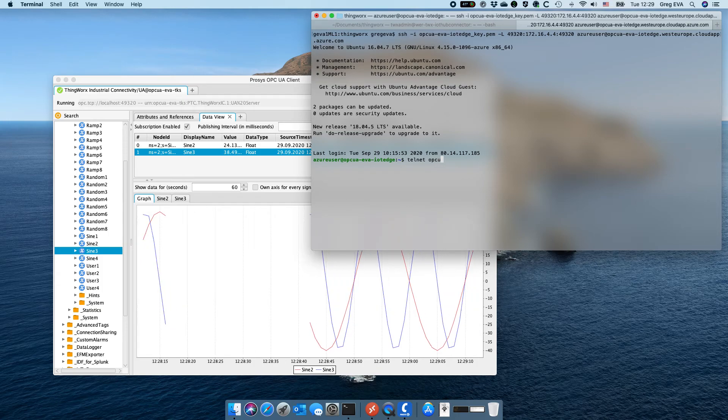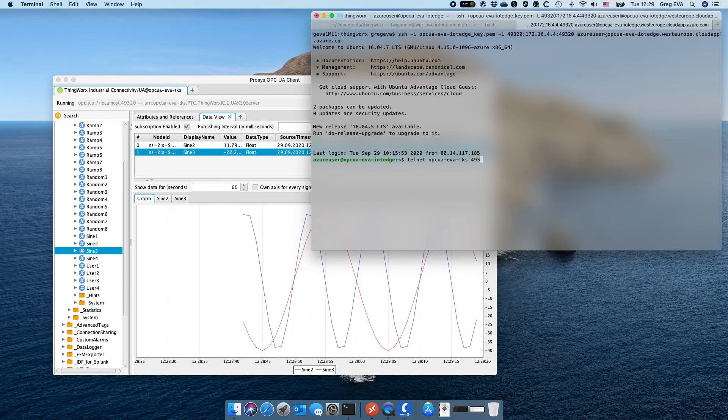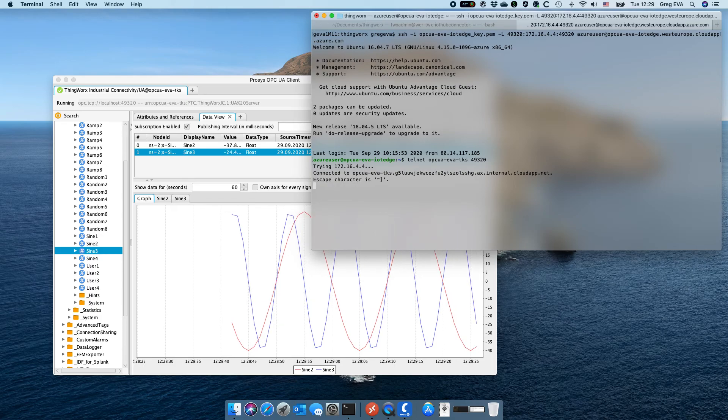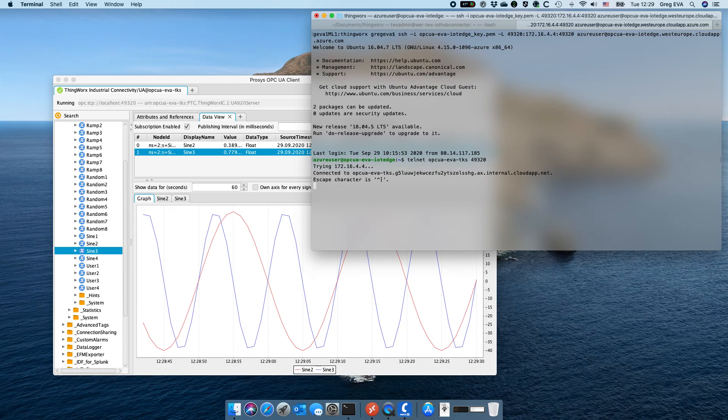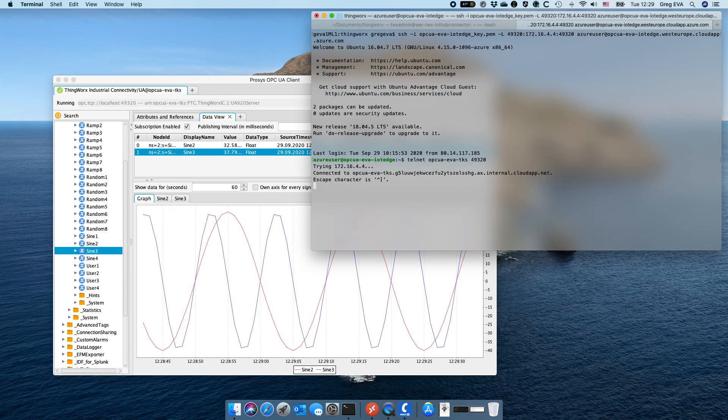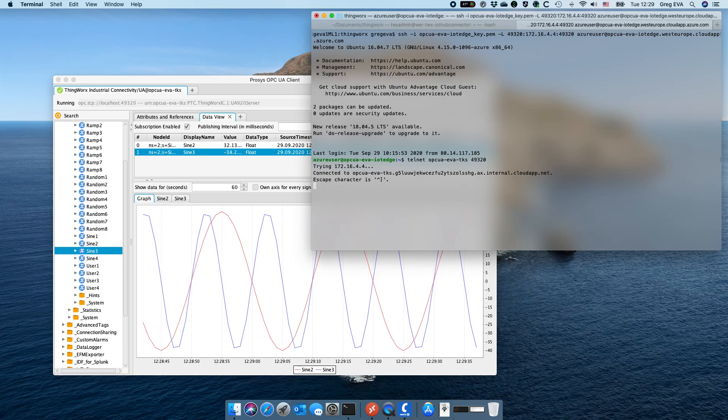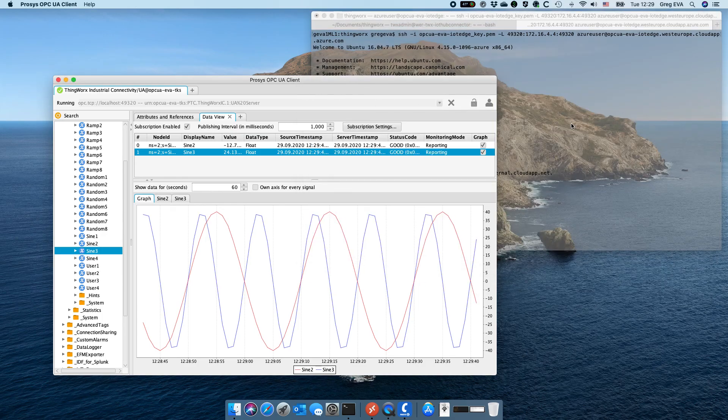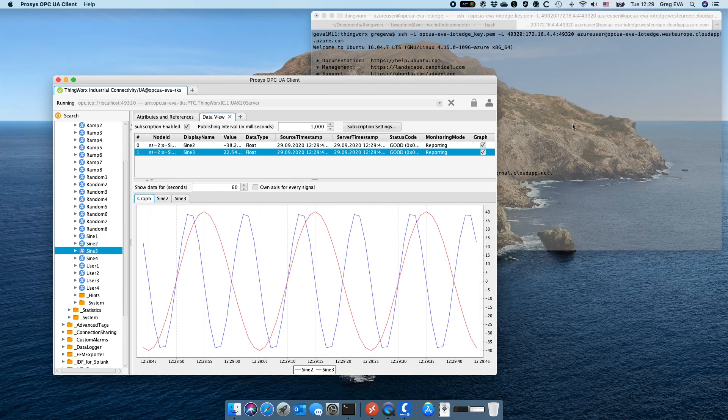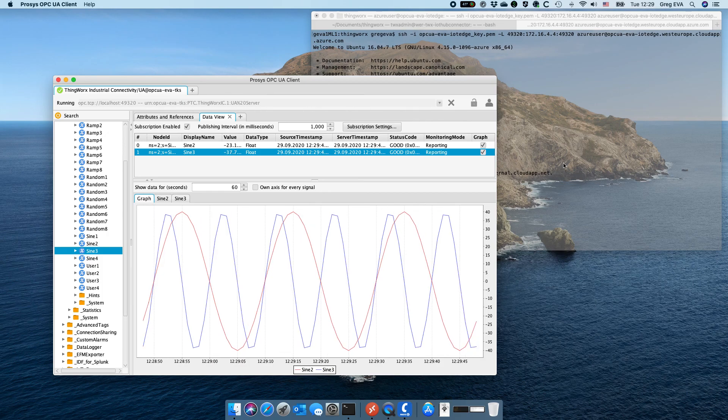One other thing that we'll try actually is right here I am on this IoT Edge device and you can use telnet to OPC UA. So these two machines are on the same network, 49320, and telnet is just going to open up a port to that particular machine. This works in this case and this is a test that we did in the particular case that I'm dealing with right now, and this test is failing. So this is a certain level of test, it's going to establish the channels open if we can open the port. But this test that I've showed you is essentially obviously it's actually using the OPC UA protocol and it's really validating the entire network connection.